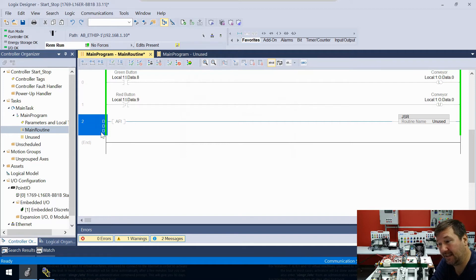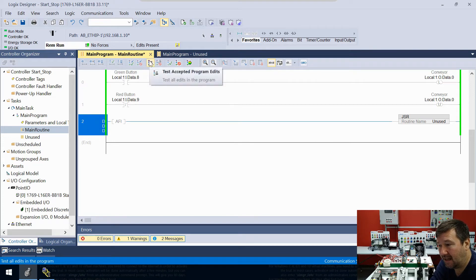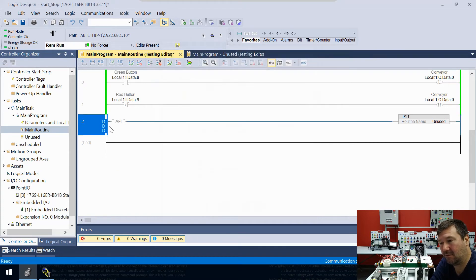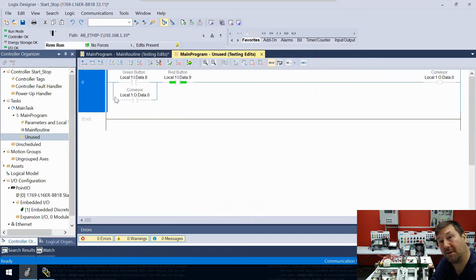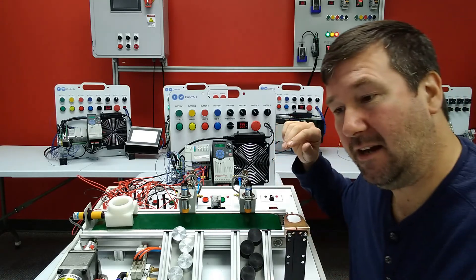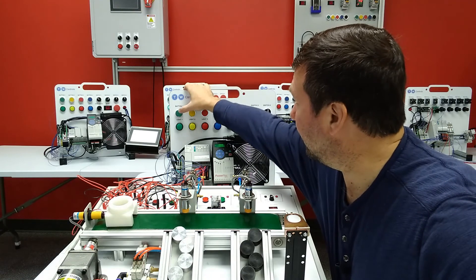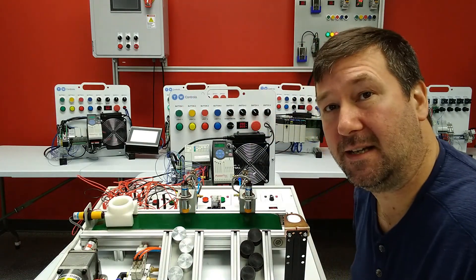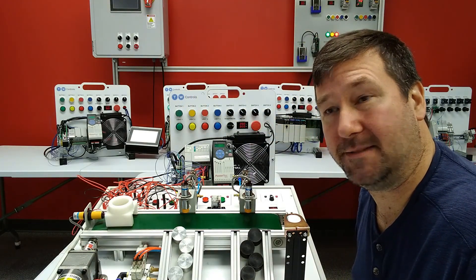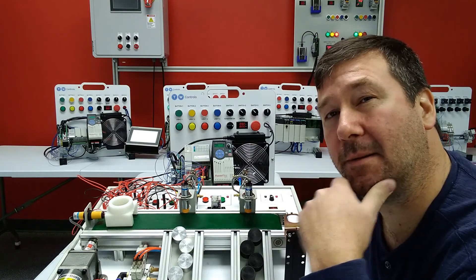Now we have capital D's, which means it is in the PLC as deleted. We don't want to use the finalize button here. Now we're not seeing the green scan bar on this rung, and if we go over to our unused routine we don't have a green scan bar there either. Let's see what happens — I'm going to start my conveyor and cycle power again.